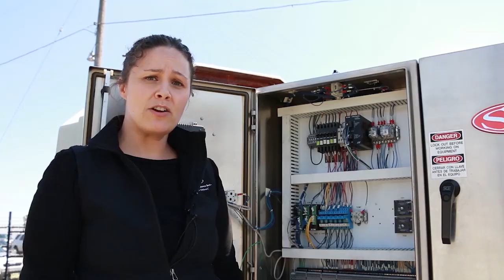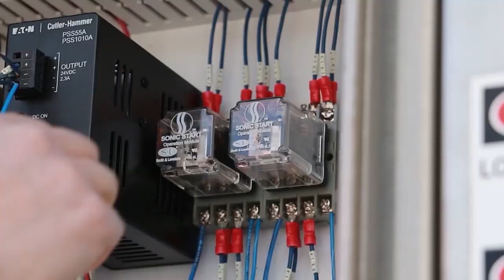Now that we are all wired up, we can go ahead and replace the old operating modules with the new Sonic Start relays. Now that our Sonic Start relays are installed, we can power up, run a cycle, and make sure there are no issues. If there are no issues, we can go ahead and do the second pump.